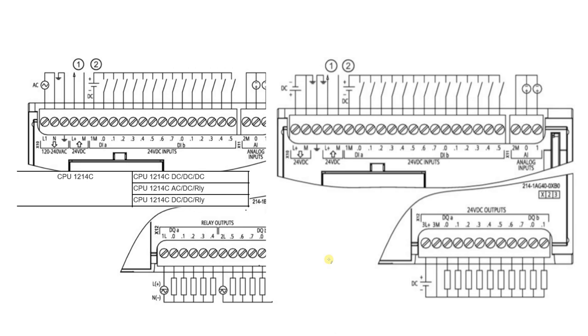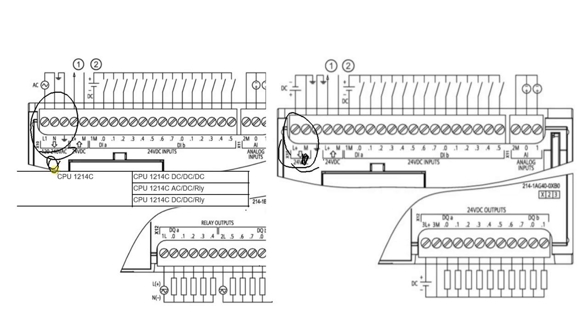So on that first part, it's either going to be AC or DC. That's the incoming power right there and right there. As you can tell, that's actually 24 volts on this one, and there's 110 or 240 volts on this one. That's the first indicator of how you're supposed to wire up the S7-1200. That's the incoming power, all of these right here.